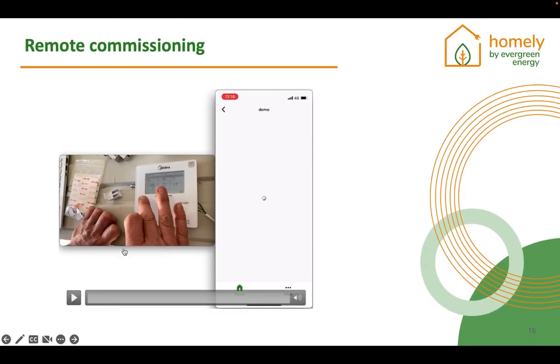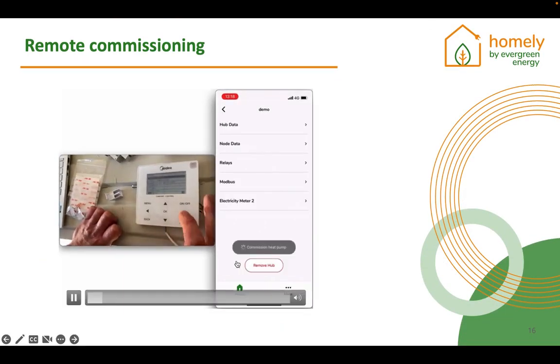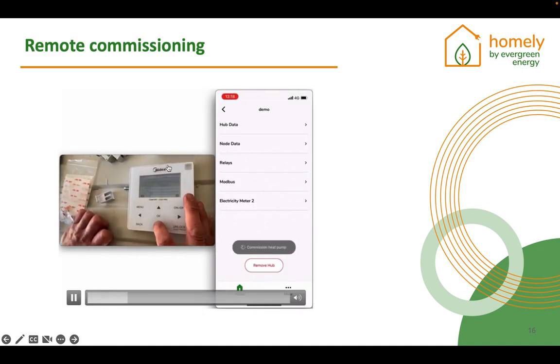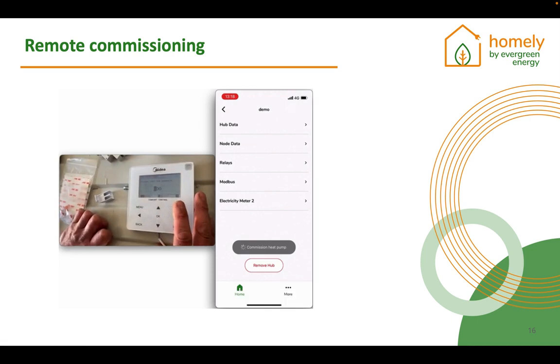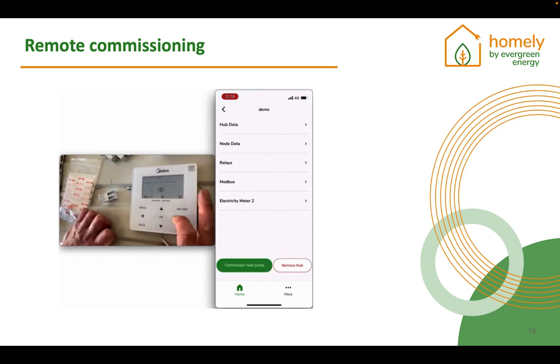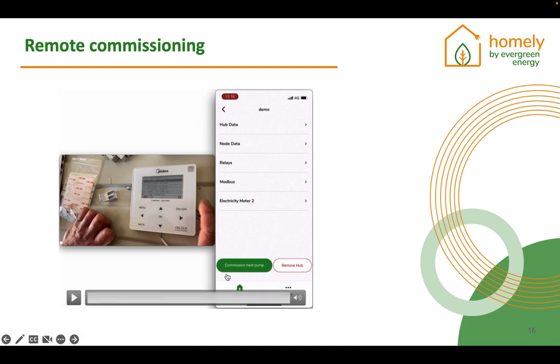I've mentioned at the very beginning that I'll talk a little bit about the remote commissioning. Remote commissioning is this button over here. So you know when you get to site and you need to enter parameters into the controller so that it sets up the controller. As an example, you need to specify where the immersion has been connected, whether it's connected to a separate timer or the heat pump itself. Here, we can actually do that all for you.